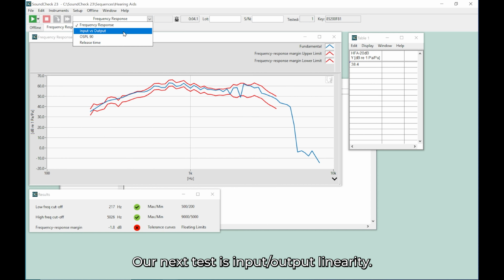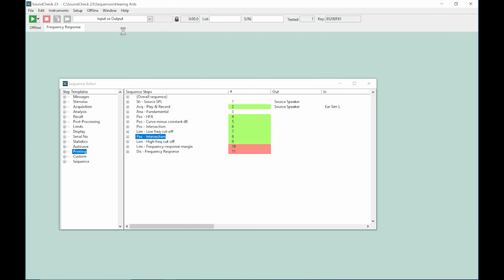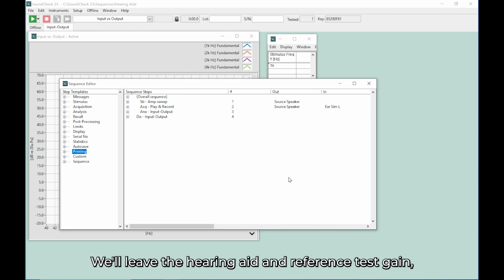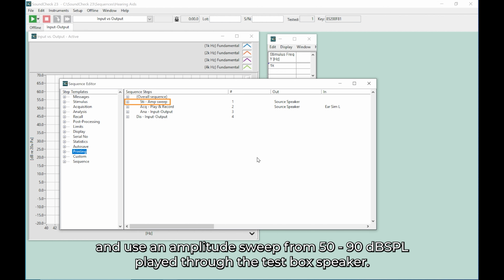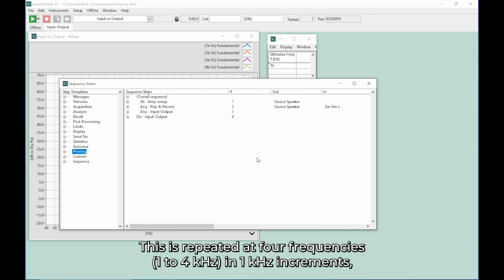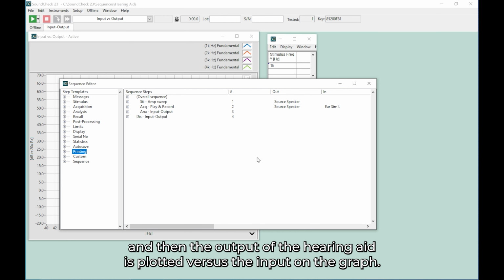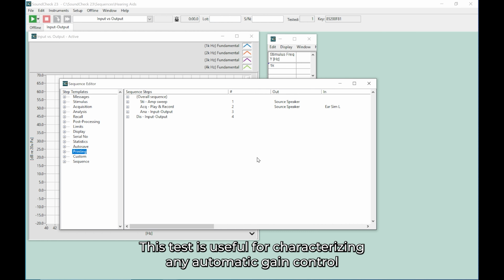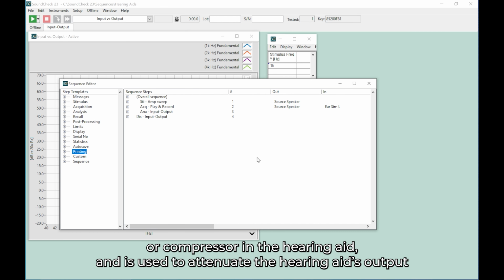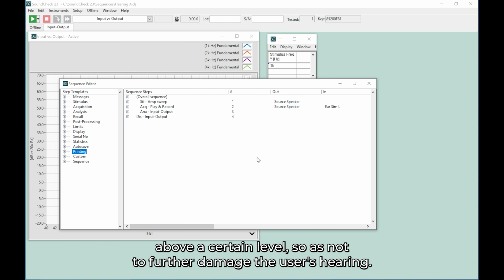Our next test is input-output linearity. We'll leave the hearing aid at reference test gain and use an amplitude sweep from 50 to 90 dB SPL played through the test box speaker. This is repeated at 4 frequencies, 1 to 4 kHz, in 1 kHz increments, and then the output of the hearing aid is plotted versus the input on the graph. This test is useful for characterizing any automatic gain control or compressor in the hearing aid, and is used to attenuate the hearing aid's output above a certain level so as not to further damage the user's hearing. So let's run it now.